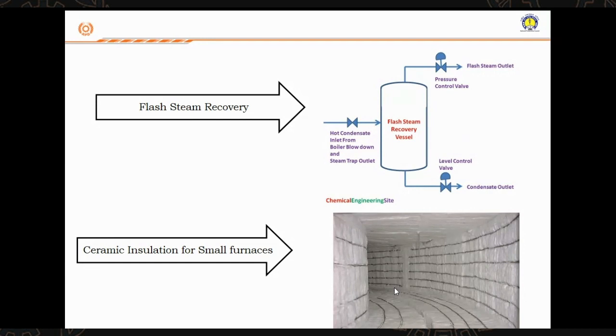Then you have ceramic insulation for small furnaces in the SMEs, like a re-rolling mill. The surface losses will be very high, and the insulation will be pretty old. Maybe they have not changed it. When you measure the surface temperature, anything 50 plus above ambient shows that there are enough radiation losses. Radiation losses mean you are losing fuel, and also affecting the environment. So you have this ceramic insulation, not like refractory bricks. It can be folded in any form, is very efficient, and has a great advantage of retaining the heat inside the furnace, right?